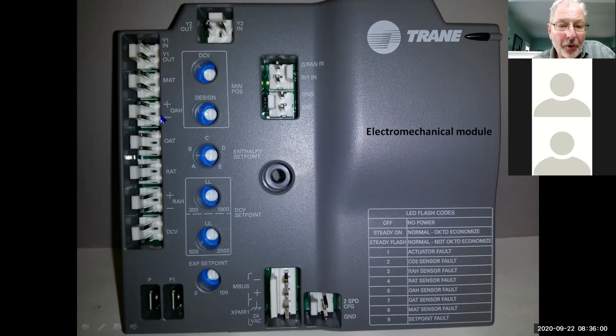We can add outdoor humidity. We can add outdoor temperature. We can add return air temperature, return air humidity. We can do averaging. But typically the only wires you're going to see on here are the MAT, mixed air temperature, okay? Or the Y in, Y out if it's an electromechanical system.